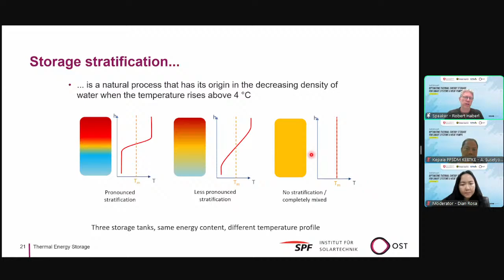A temperature sensor in the upper storage area registers hot for perfect stratification, but only lukewarm in the unstratified case. So how does this look in a storage tank? There we have stratified versus a non-stratified storage charging with solar thermal collectors. You see here a storage tank with temperature sensors on the wall of the storage tank. You see this in the graphic beside. In the first case, you have an immersed heat exchanger, non-stratified. That means you put in the heat on the lower part of the storage tank. And you see the temperature increases simultaneously on the different heights of the storage tank, meaning the collector return temperature also rises, and that means the efficiency of the solar collectors decreases.